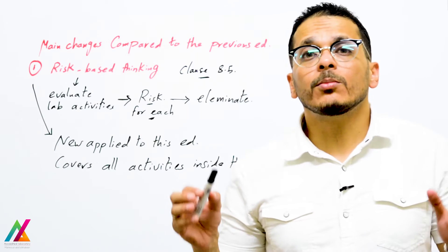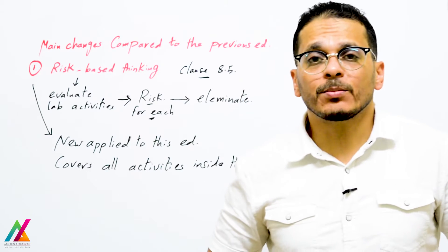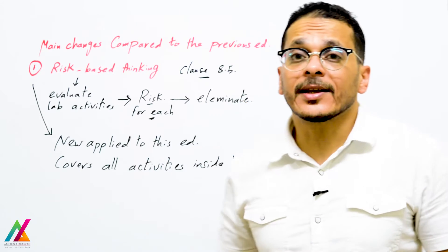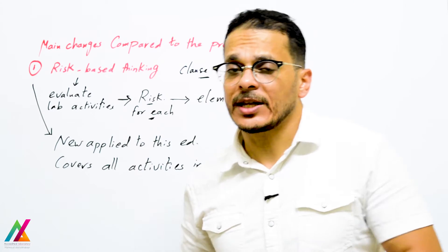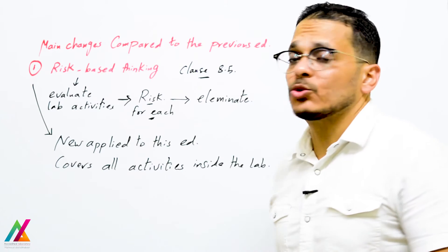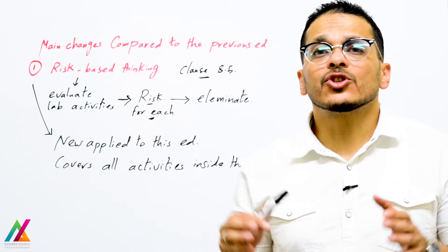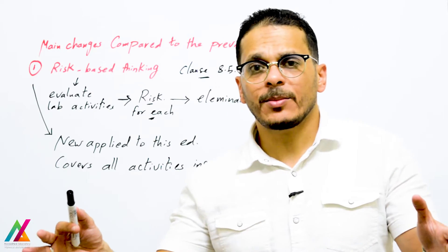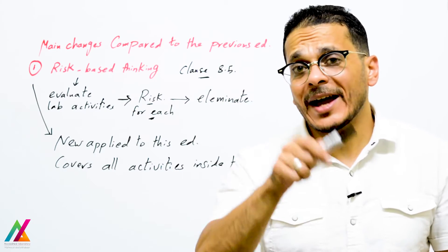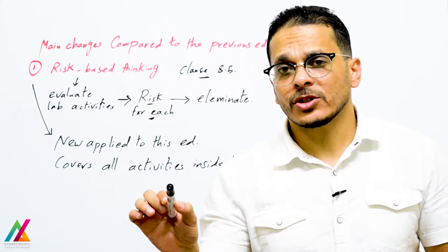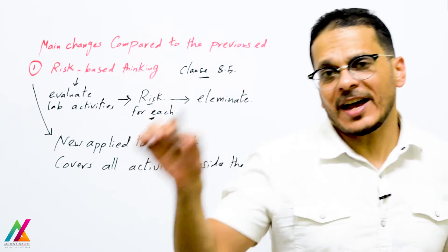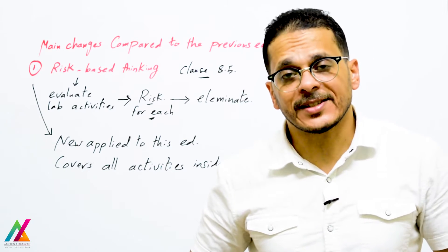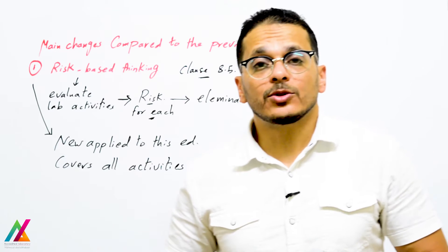The most important change compared to the previous edition is risk-based thinking, or the risk-based approach. This is explained in detail in clause 8.5, 'Actions to Address Risks and Opportunities.' This is a new addition to this edition and covers all activities inside the lab. You shall evaluate all activities inside the lab and for each activity try to identify what risk may affect it, then eliminate or reduce that risk.